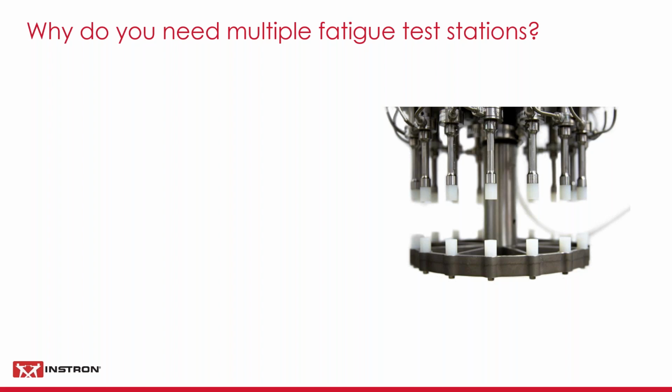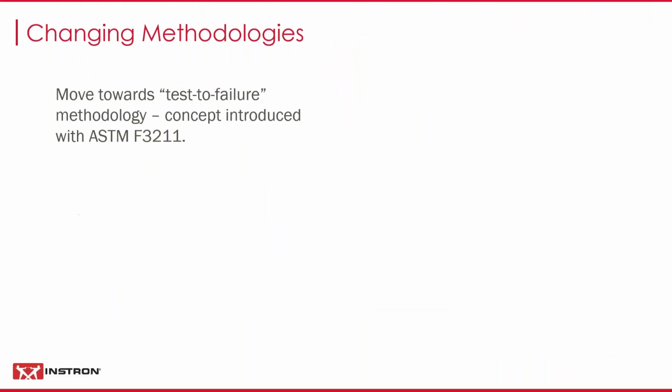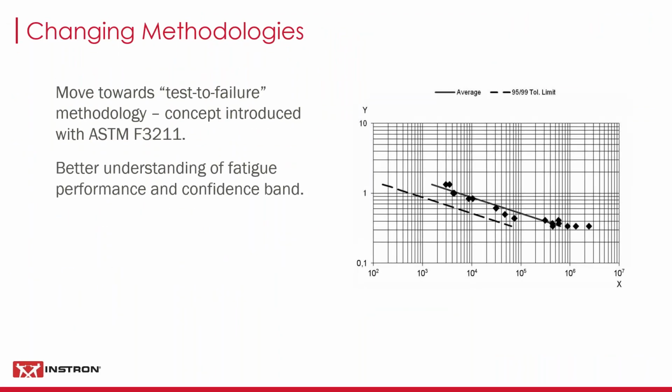Okay. Well, I'm not so sure about the proof test aspect of it with the original, it's just pass/fail. I don't think I'd see any particular problem with that, but you wouldn't really see a particular value in it either. You start looking at the test-to-failure approach, so the F3211 approach, which I mentioned here. At that point, it is definitely worth understanding what happens.